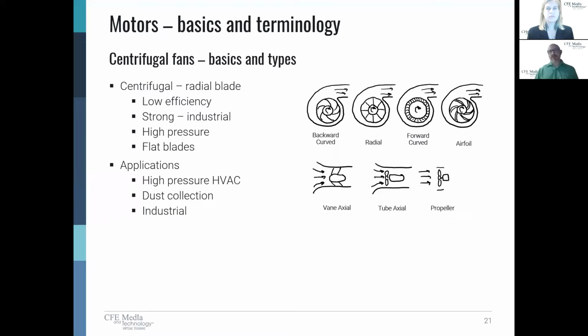Radial is going to be probably your least efficient. It's also going to be fairly noisy. It's going to be capable of high pressure, but for the most part, we're not going to see these very often in HVAC unless we're dealing with really, really high pressures. But because of the low efficiency, it's probably not the best selection.